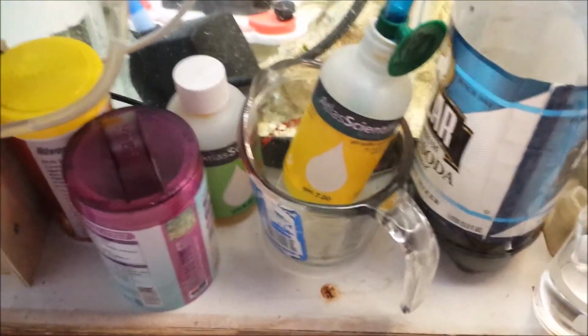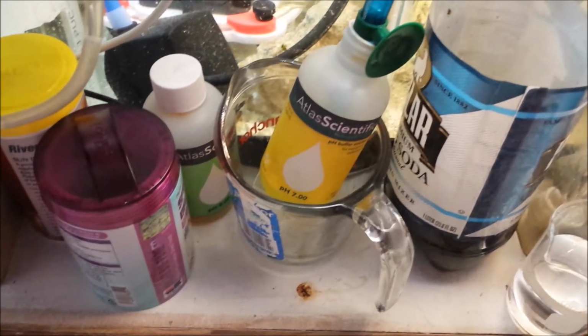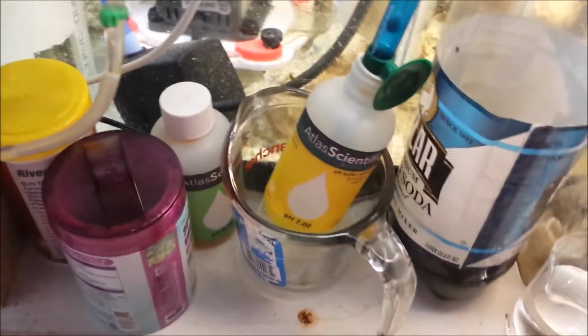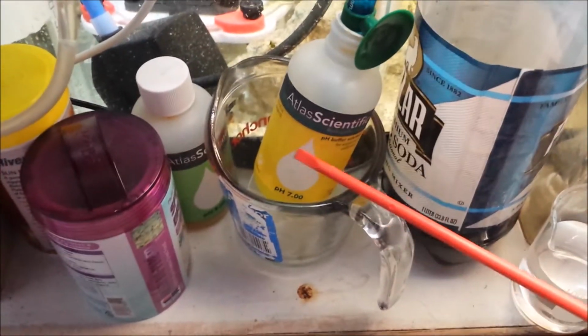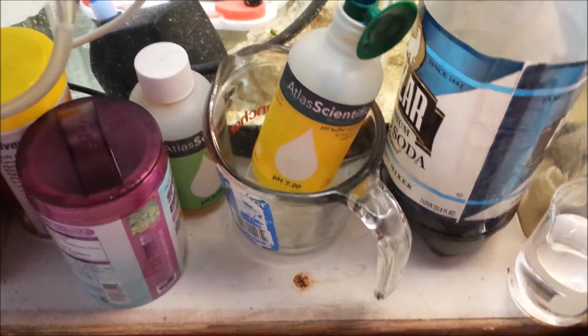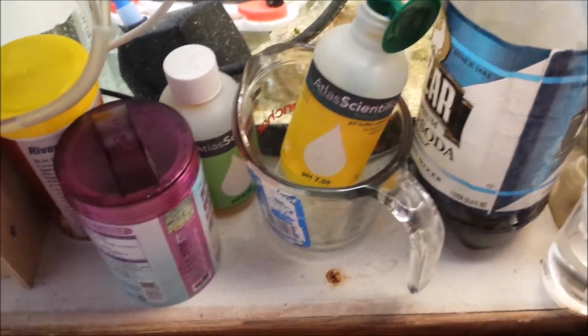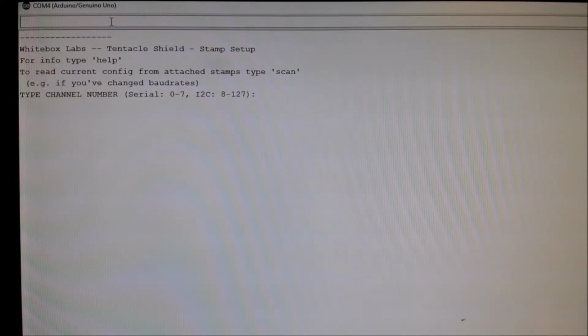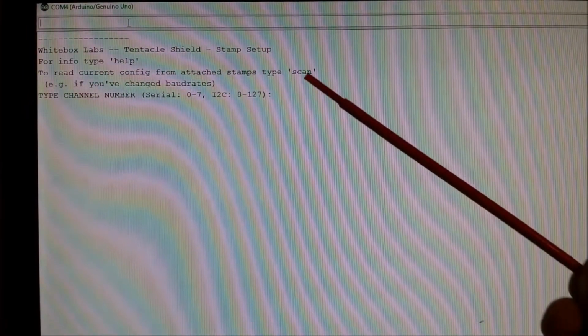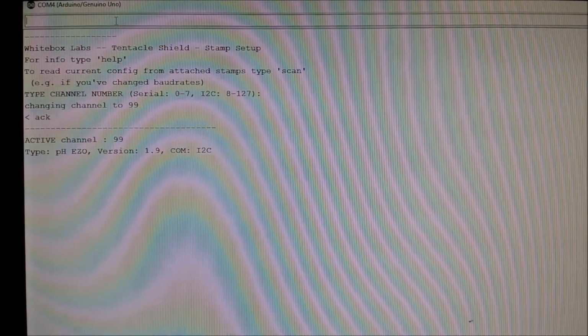Now, Atlas does recommend 3-point, and unfortunately I don't have any 4. So probably the best solution would be to use the 7 as your mid, the 4 as your low, and the 10 as your high. Okay, so I'm going to run through the calibration procedure, including temperature compensation. I have the phone position here. Hopefully you can read what I'm doing. So the first thing to do is type 99 and then press enter. That'll actually take me into that channel. And then I'm going to do cal, clear.